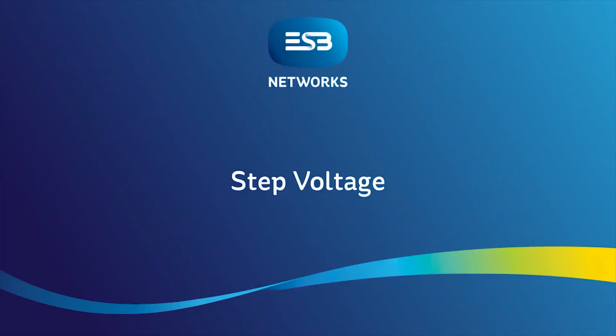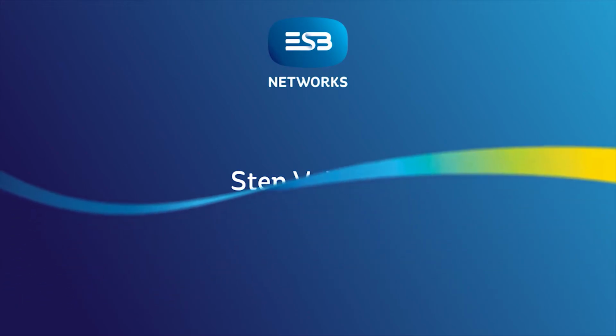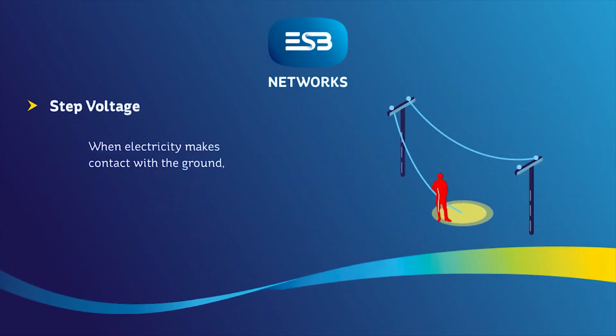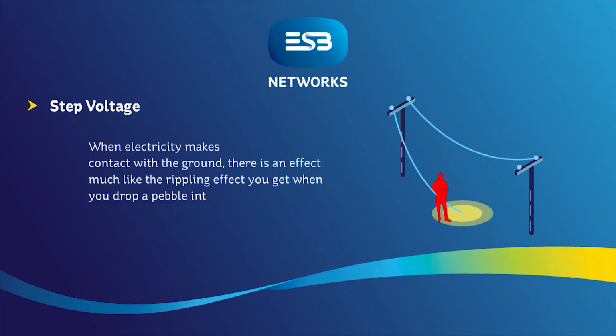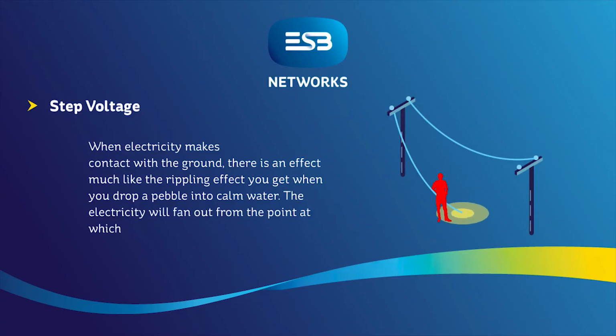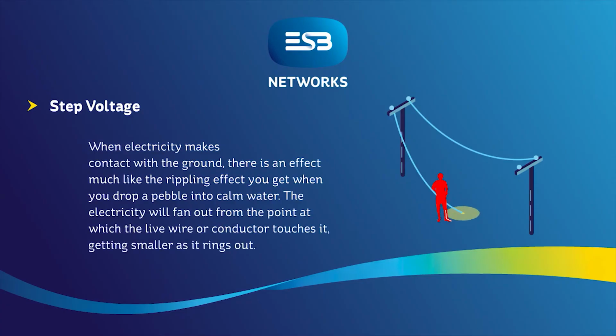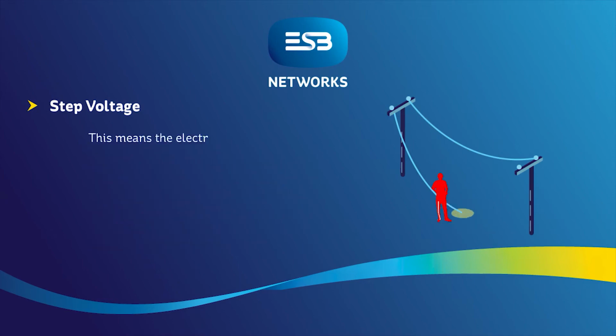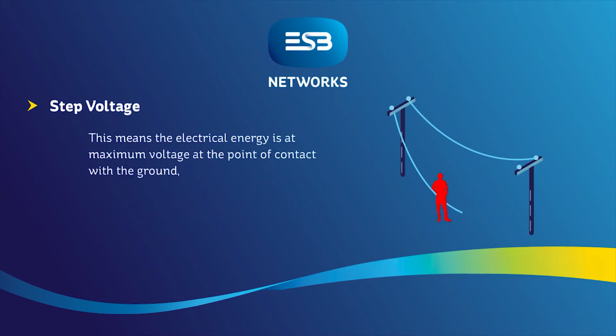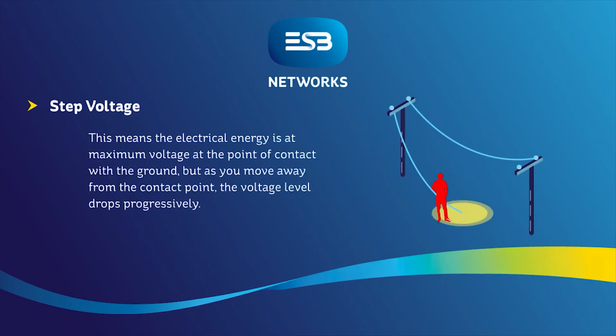Another type of voltage to be aware of is step voltage. When electricity makes contact with the ground, there is an effect much like the rippling effect you get when you drop a pebble into calm water. The electricity will fan out from the point at which the live wire or conductor touches it, getting smaller as it rings out. This means the electrical energy is at a maximum voltage at the point of contact with the ground, but as you move away from the contact point, the voltage level drops progressively.